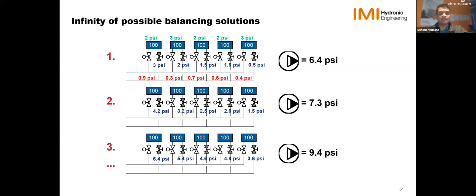This helps us save on pumping energy, because when you have properly sized the valve, we get 6.4 psi of pump head in this system. Whereas even if the system is balanced but you are not doing it properly with the right pressure drops, you're going to see a much higher pump head needed in your system. So it's important we understand all that, not just balancing but also the importance of pressure drop. That's manual balancing, and I hope that clears up why it's so important to look at balancing procedures and pressure drop when we are doing manual balancing.